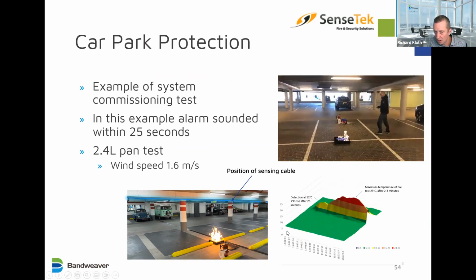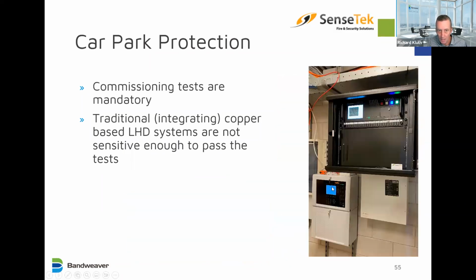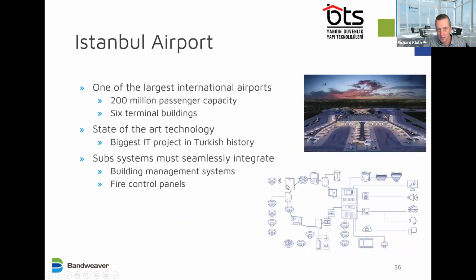Interesting that this started at 5 degrees C background temperature. The alarm actually alarmed at 12 degrees C, and the maximum temperature of this fire pan test, because we can obviously measure all around it, was only 25 degrees C. There wasn't too much spreading along the length of the cable, so you wouldn't be able to pass these fire pan tests with conventional linear heat detection. And this is becoming the de facto standard in the Netherlands for car park monitoring. As we said, tests are mandatory, and copper-based systems are not sensitive enough to pass this.